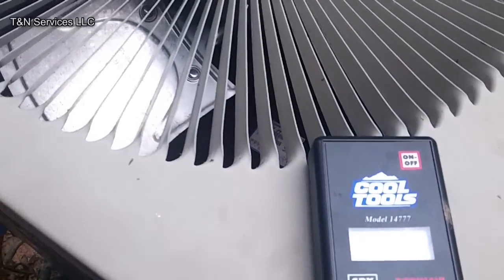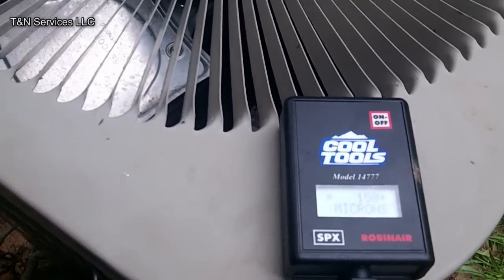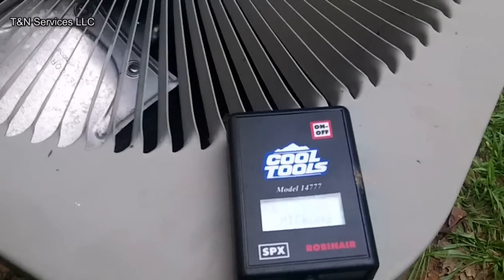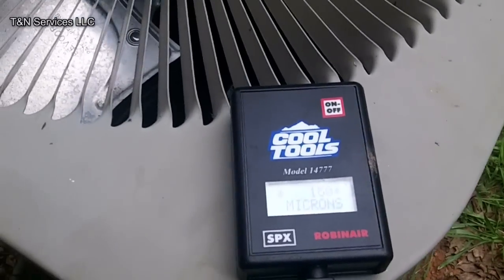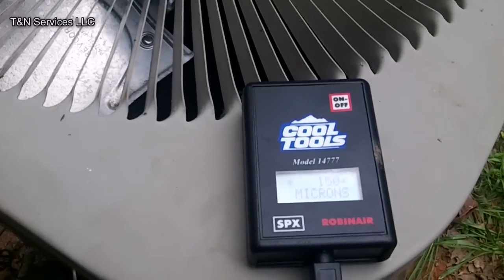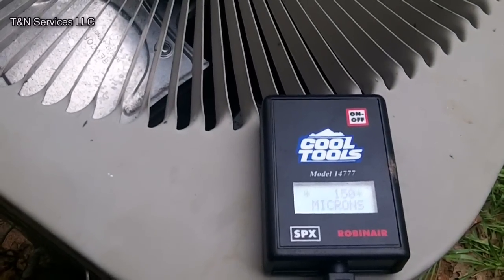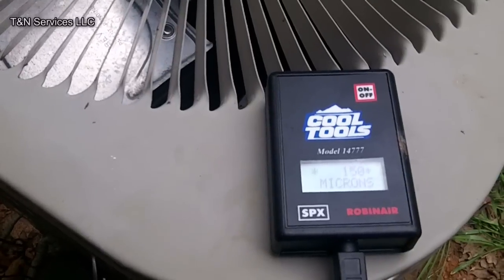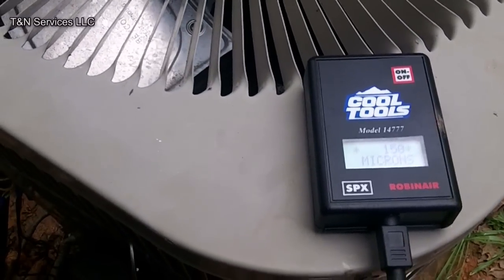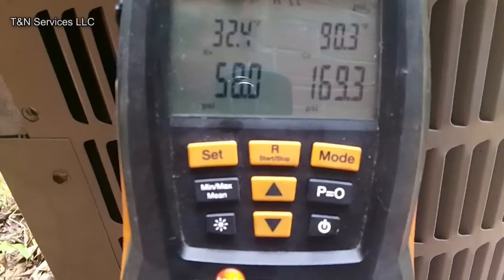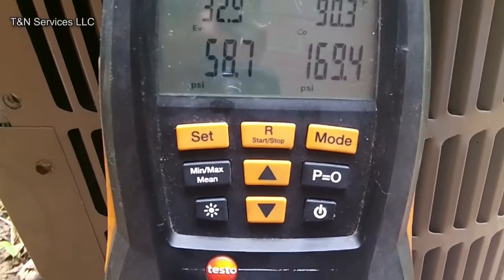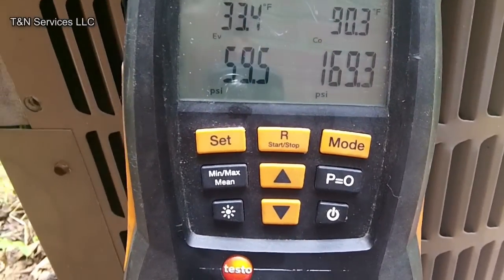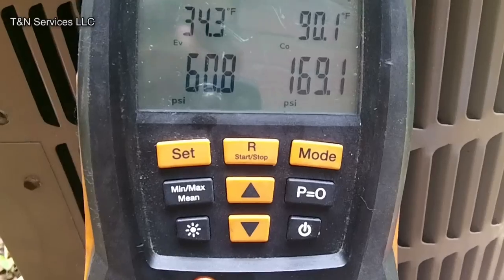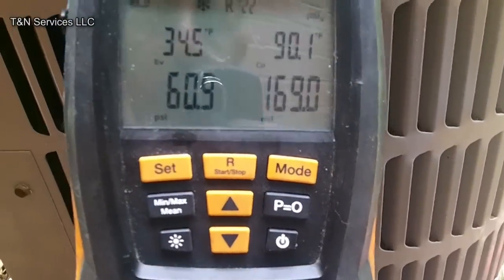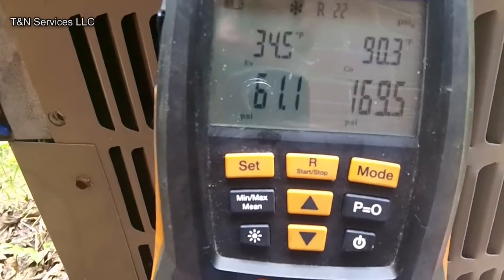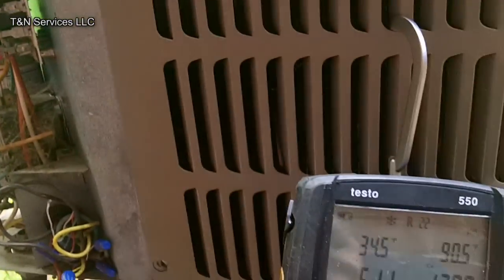Go back in there, put the thing back together, and hopefully by then, well, there's no hopefully to it, we're already down in 150. So the vacuum will be pulled, and we'll be ready to start it up. Alright, I just got it started up, and I'm waiting on my little compadre to bring a tool bag to me so I can put my temperature probe on here so I can check superheat and put everything back together.